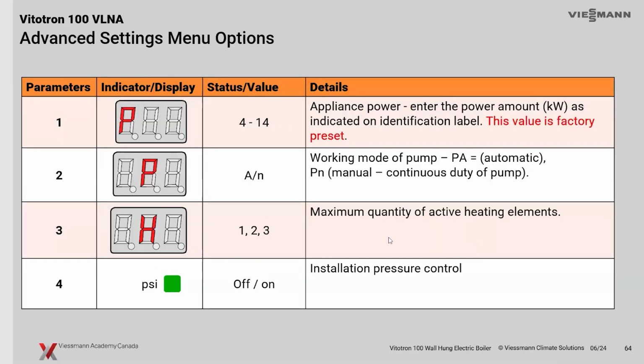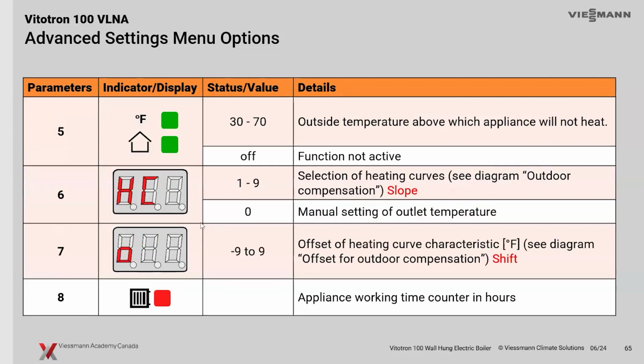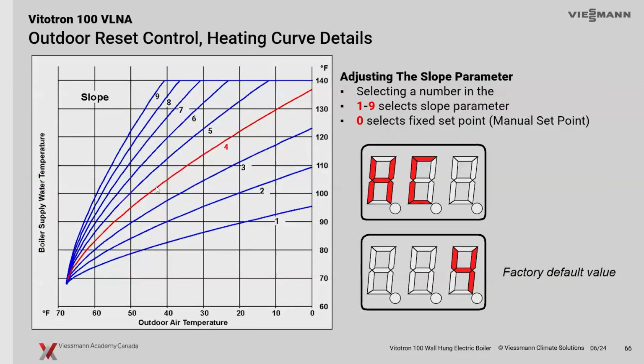And the most important one I want to talk about right now really is setting up your heating curve. So if I go to parameter 6 here, heating curve, I can make my adjustments of my slope or my shift in this area. So if I'm doing outdoor reset, the extra step is I've got to go into this advanced programming, these advanced settings, hold that little arrow key down, push the standby button, and then go to parameter 6 here, and I can make those adjustments of my slope and my shift on my system here.